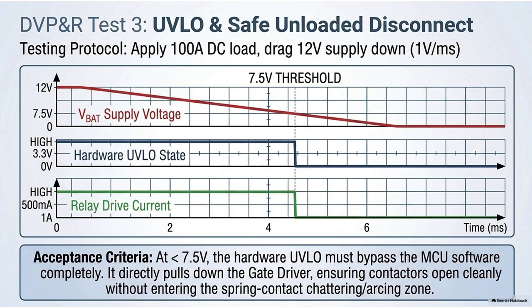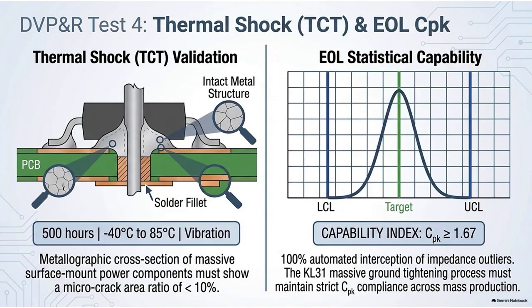High-speed, high-voltage oscilloscopes are wired directly across the contactor terminals. What are they looking for on the oscilloscope trace? They're looking for a completely clean voltage step. To pass validation, there must be absolutely zero chattering and zero duration of plasma arcing under that 100-amp load. The physical separation of the copper pads driven by the internal springs must be instantaneous and absolute, cleanly breaking the high-voltage circuit, even as the low-voltage supply driving it collapses. It is the ultimate proof of the hardware dead man switch.